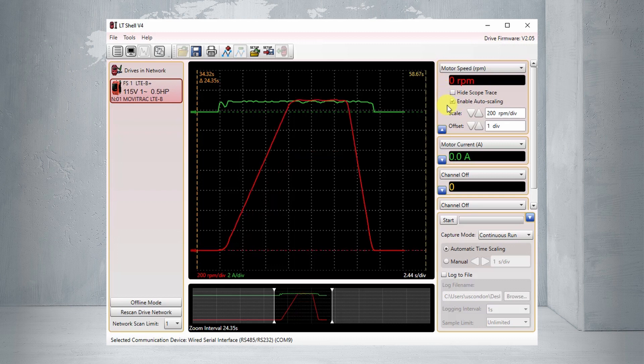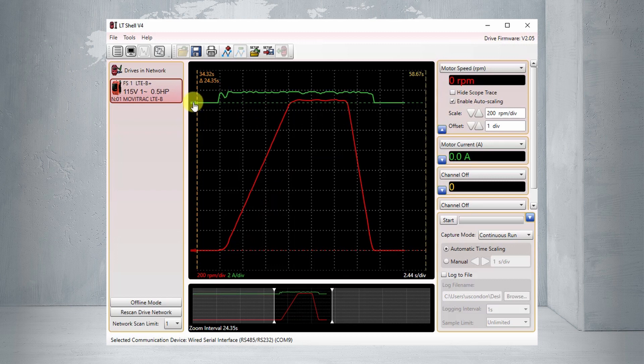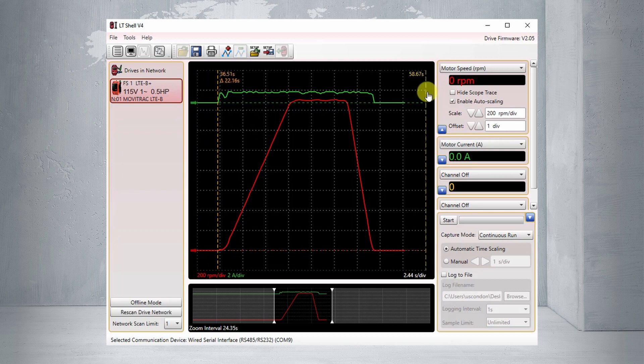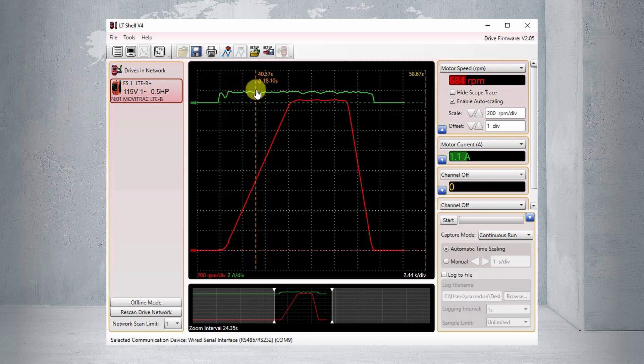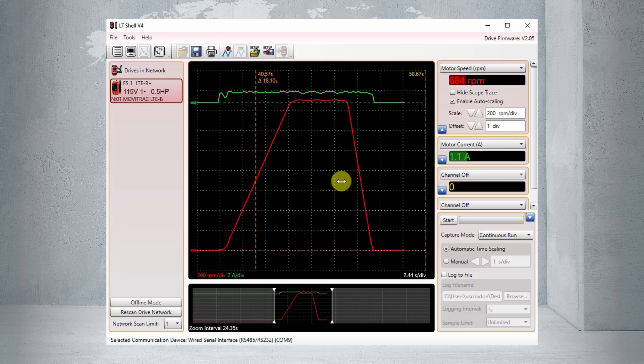I'll open the channel and enable auto scaling on the motor speed channel so it zooms up to the maximum. When you're taking measurements, it's often a good idea to magnify as much as you can — it makes taking accurate measurements easier. We can see how the drive behaved, how it ramped up to speed, and how the motor current changed while accelerating. Grabbing the cursor on the left side and dragging it to roughly the middle shows that at that point the speed was 684 RPM, and the current was drawing 1.1 amps — useful for looking at instantaneous values of the plot.